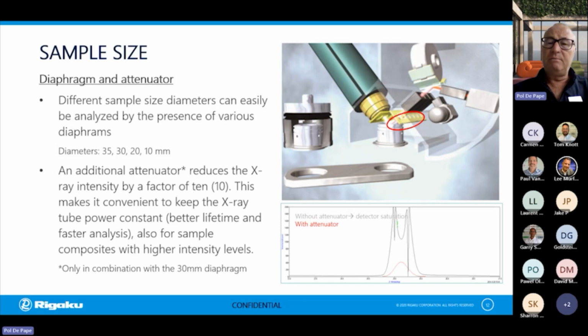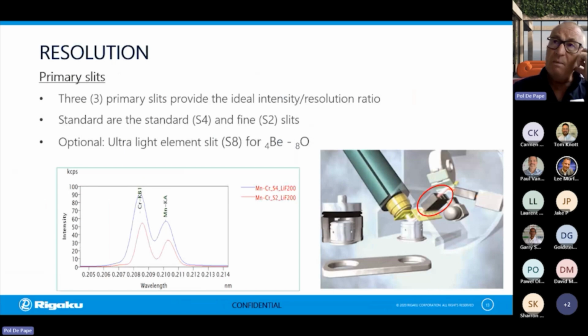And we can see on the right picture below what happens if I use an attenuator or not. The gray scan really shows a detector signal without using the attenuator, so we can clearly see saturation of the detector. And then with the attenuator, we can observe a very nice peak. So this really helps to keep our system stable, but also to reduce our measurement time. So basically, we can offer 3 collimators. We have positions for 3 collimators, which come after the sample masks, of which 2 are standard, and we can have one additional one for those who want to analyze light elements from beryllium to oxygen.